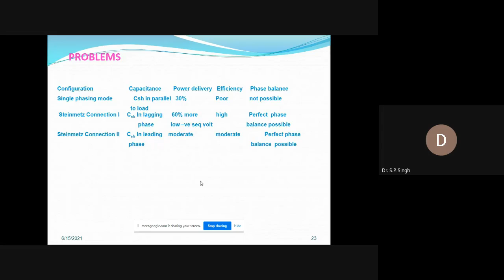This is another kind of connection for star connected machines. Again, the limitation of the star connection machine is you will never get the output power more than 30% of the rated power of the machine, when this machine is working as a single phase.